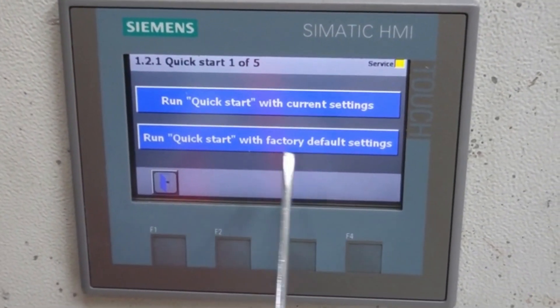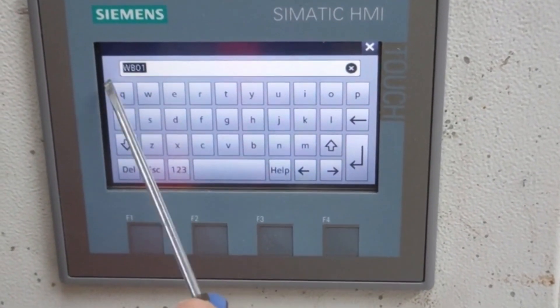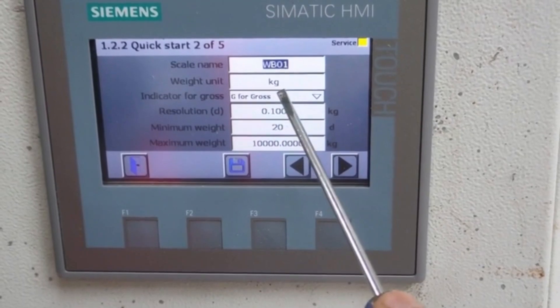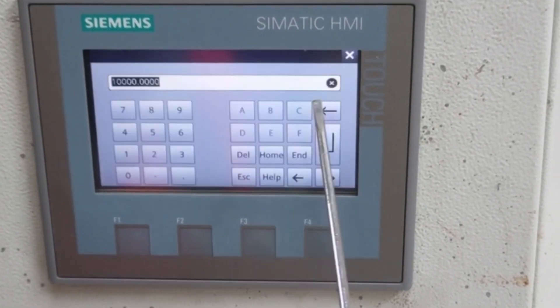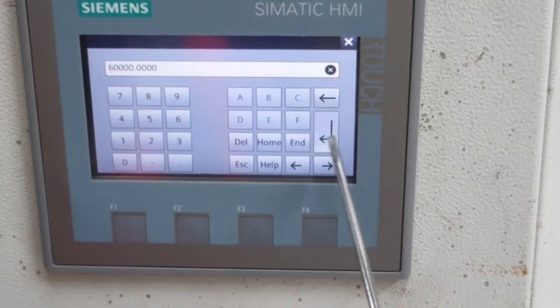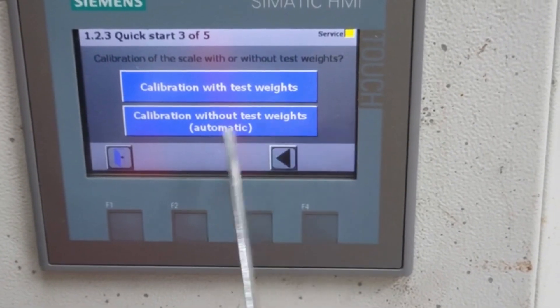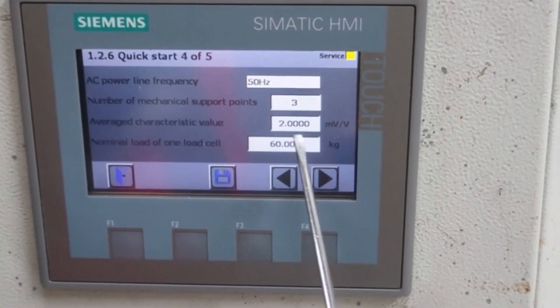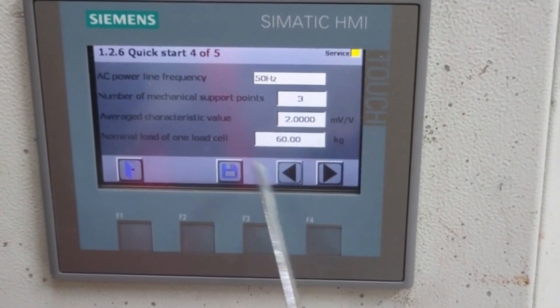I will go with 'Run Quick start with current settings.' Here you can give the weigh bridge name — I have set it as Weigh Bridge 01. Weight unit you can set as kg, tonne, or gram as you wish. Set the gross weight resolution. I have set the maximum weight as 10,000 kg (10 tonnes), or you can set it as 60,000 kg (60 tonnes). Now for calibration, there are two options: calibration with test weight and calibration without test weight. Calibration without test weight requires the actual load cell parameters — number of load cells, millivolt per volt, and load cell capacity.